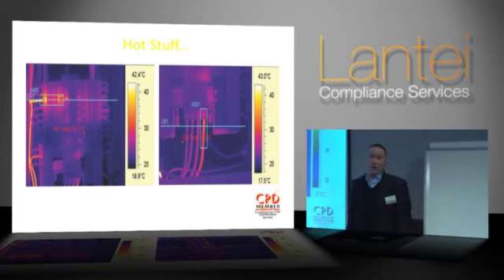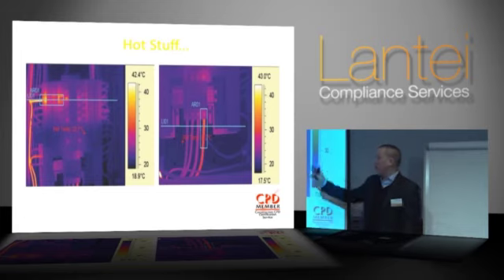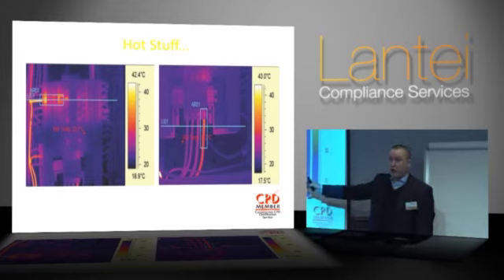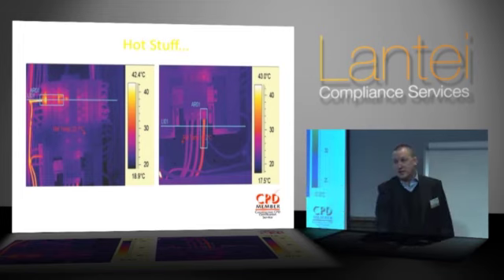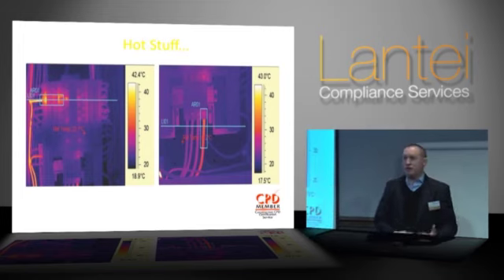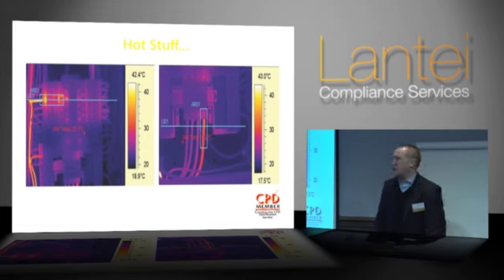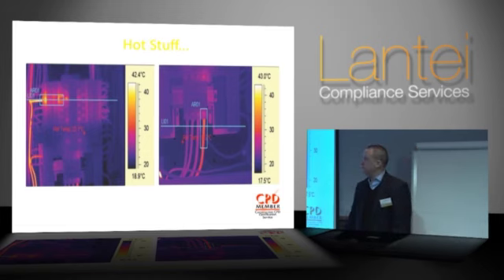On this particular site, thermal imaging was done first. That image led us to believe there were harmonic distortion issues, so we recommended mains analysis be carried out, which gave us a much more in-depth understanding of what the problems were and where they were.